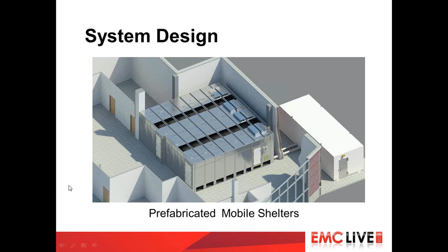A lot of the verification testing that goes on for HEMP IEMI protection, some of the special testing, is pulse current injection testing. This is where very large currents and voltages are directly injected into the conductors passing through the filter elements, and the measurements are made on the load side of the filter elements. So on the line side they get injected. In order to pass the limit with a 2500 amp injection, you can only let through less than 10 amps on the load side of the filter. So it's very important to make sure that you've got certified filters that you're using in the facility for your protection.